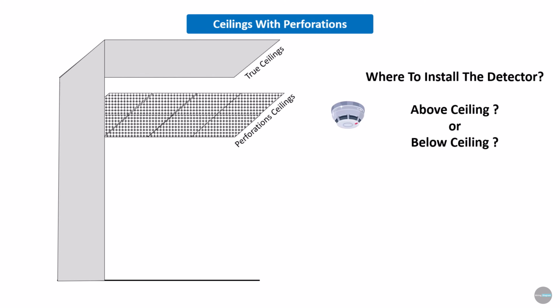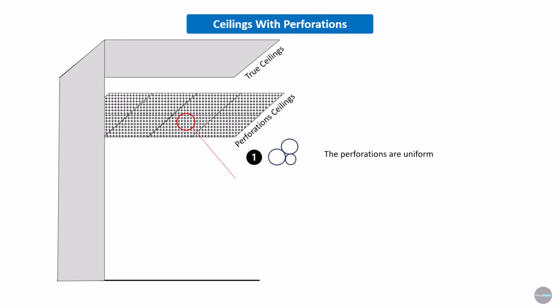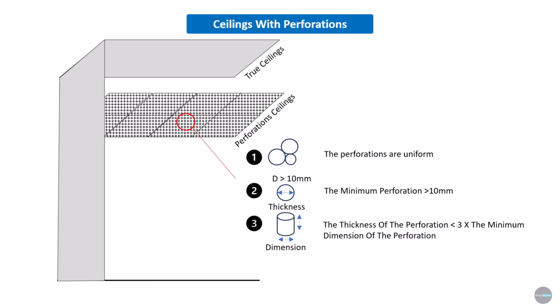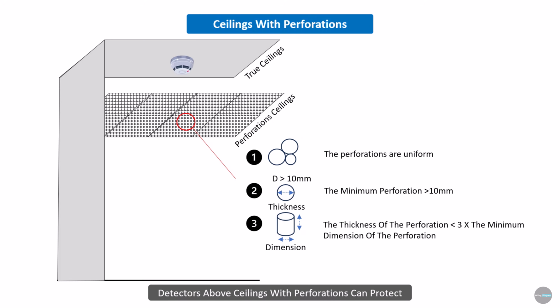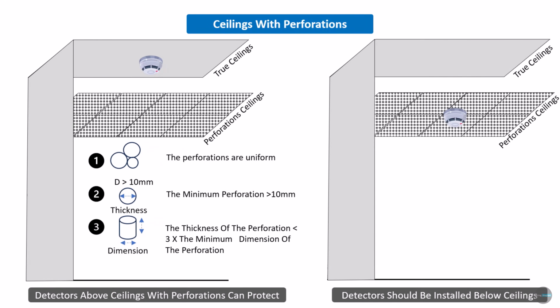When a ceiling has perforations, the detector must be installed above the ceiling if the following conditions are met. First, the perforations are uniform in size. Second, each perforation is larger than 10 millimeters. Third, the thickness of the perforated material is less than 3 times the minimum dimension of the perforation. In such cases, mounting the detector above the perforated ceiling ensures proper smoke detection and accurate system response.